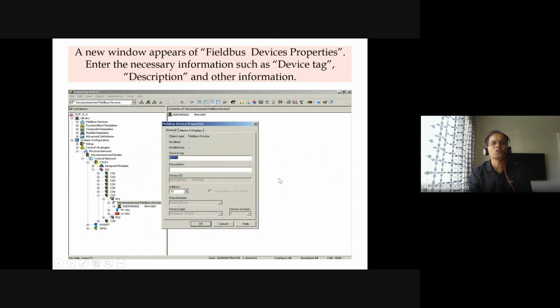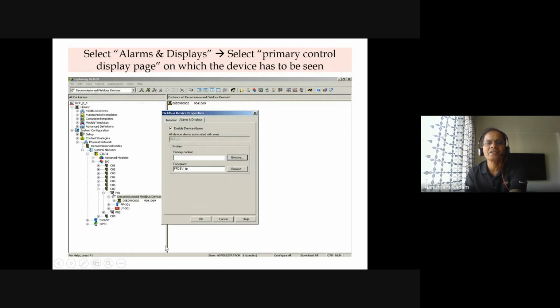Then a new window appears for Fieldbus Device Properties, where you enter necessary info such as device tag, description, and other information. The moment you connect any new device, the manufacturer's tag is automatically displayed, and only then do we give our own tag name to the device, like PDT1, just for demonstration purpose, and go ahead.